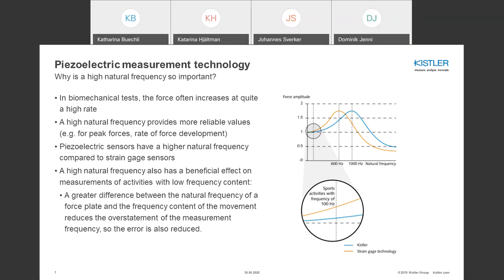A high natural frequency is important in human movements because forces increase at a high rate. Thanks to a high natural frequency, peak forces and the rate of force development can be measured more reliably. A graphic comparing two force plates with different natural frequencies shows that the higher the natural frequency, the lower the overstatement of the signal — for example, at an activity frequency of 100 Hz. A greater difference between natural frequency and signal frequency reduces overstatement and error.